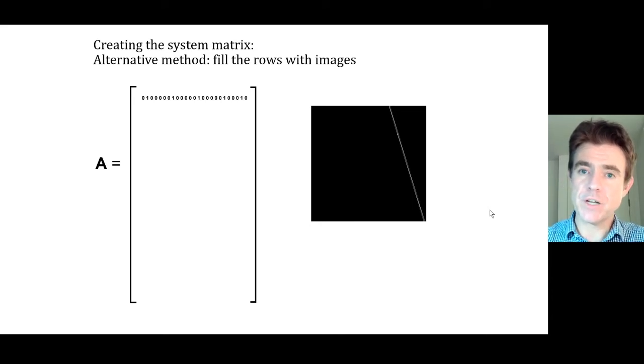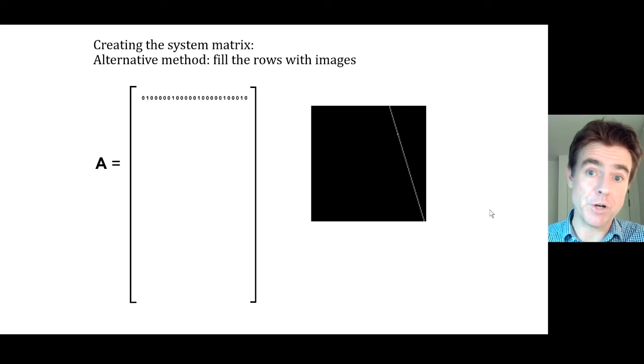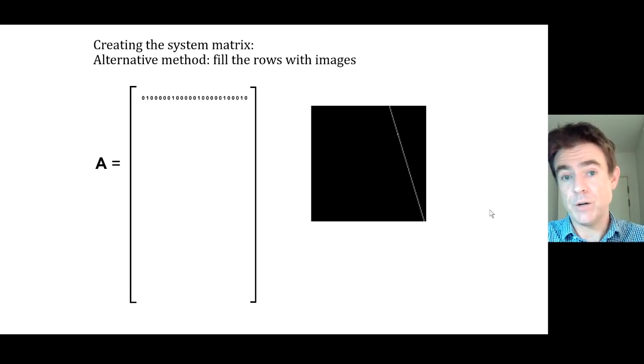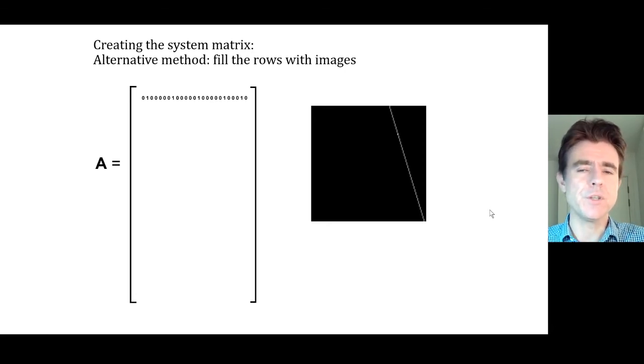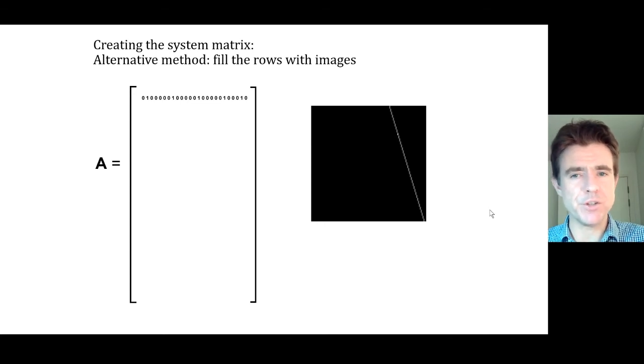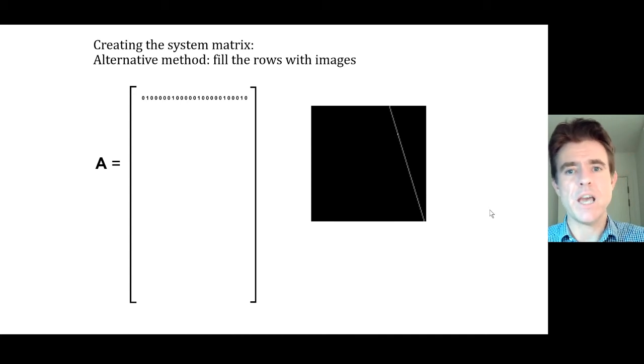It's like a weighted collection of columns of the system matrix being the forward projection process. If you put in an arbitrary parameter vector — a collection of weights for different point sources — that corresponds to a collection of weights for the various sinograms; you just add them all together and that gives you the modeled sinogram. Alternatively, we could consider rows of that matrix. This matrix is often referred to as the discrete X-ray transform — some call it the discrete Radon transform, but that's only really the case for 2D. For 2D and 3D it's safer to call it the X-ray transform, since the 3D Radon transform deals with planar integrals, not line integrals.